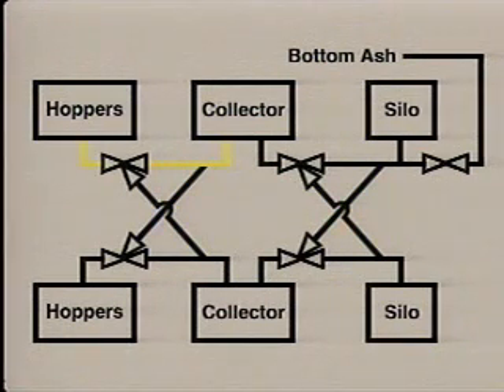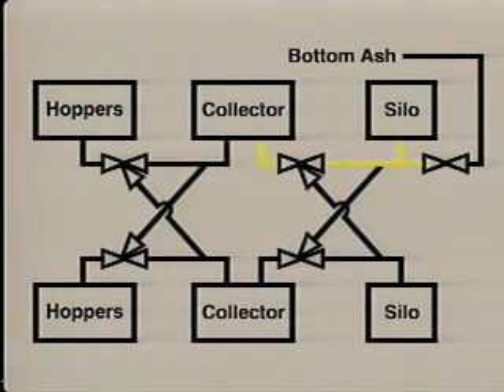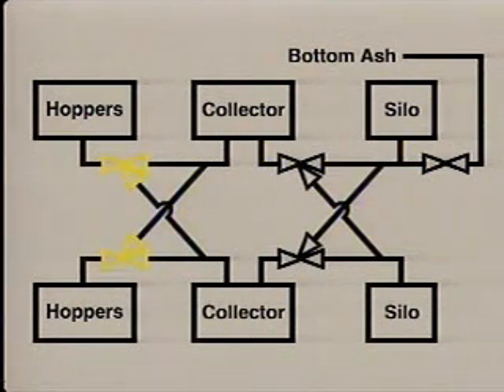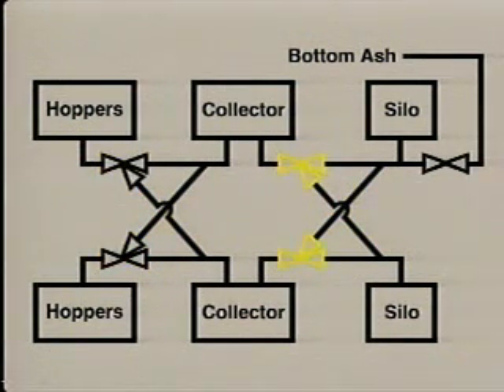Each system uses a vacuum pump, which is not shown, to suck fly ash from the hoppers into the collector, and a pressure blower, which is also not shown, to blow the fly ash from the collector into the silo. To add a degree of flexibility, the process contains two collector crossover valves and two silo crossover valves.